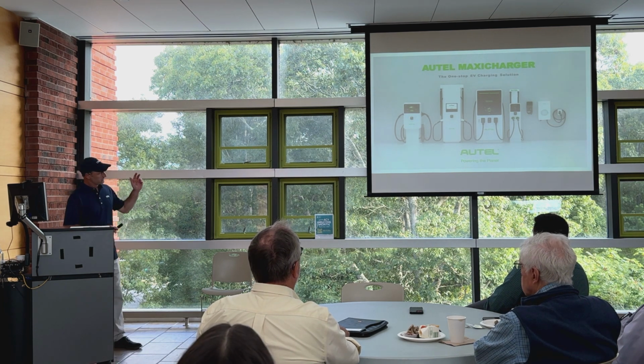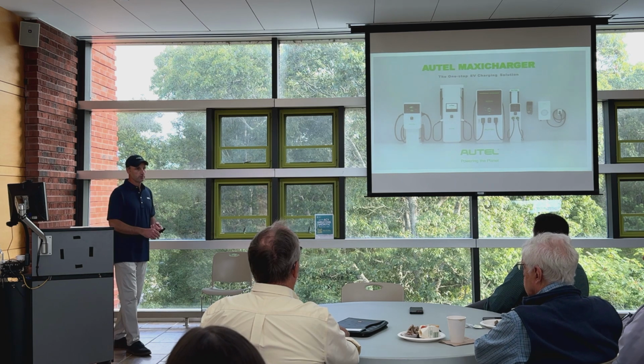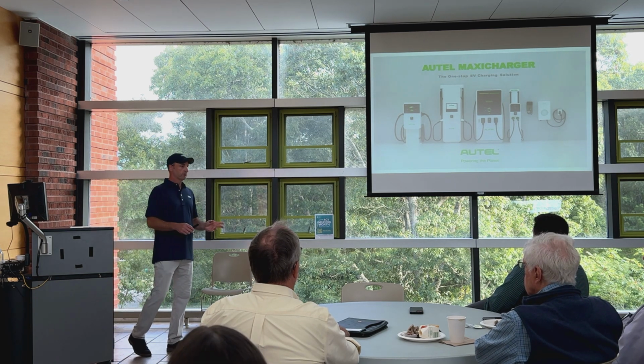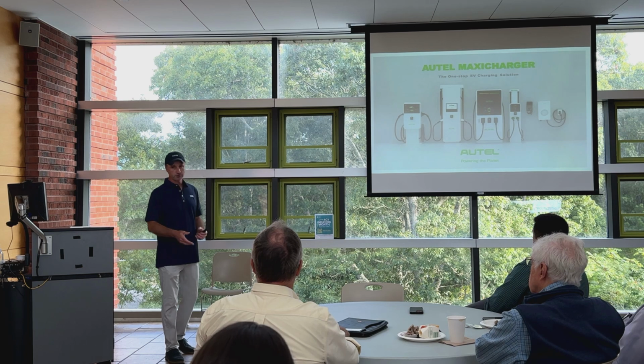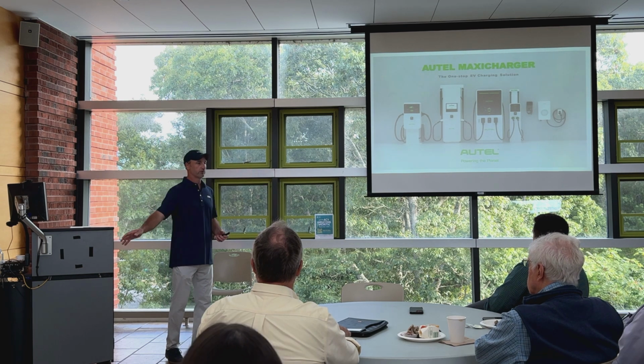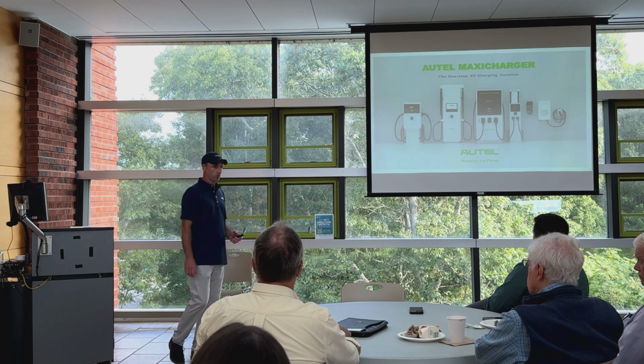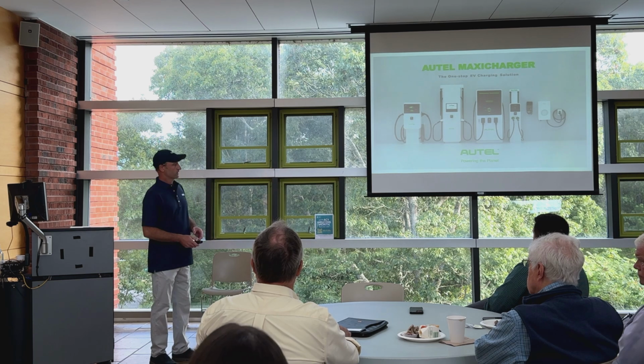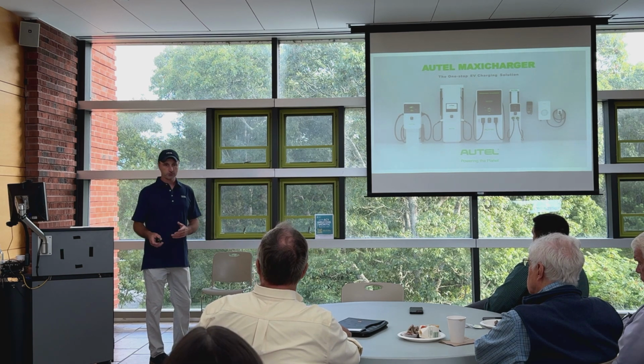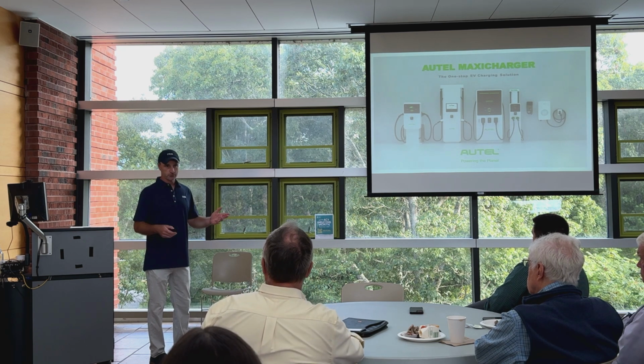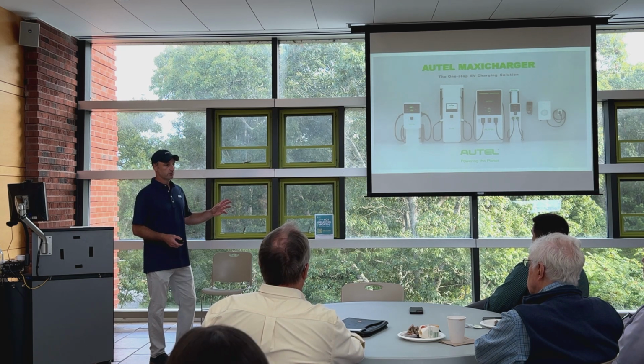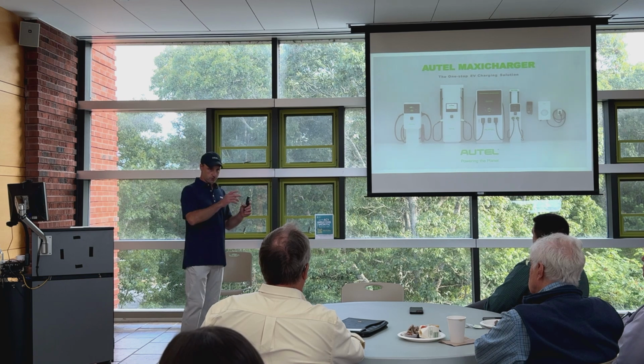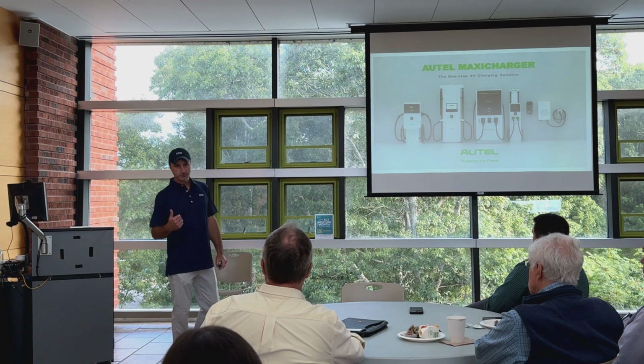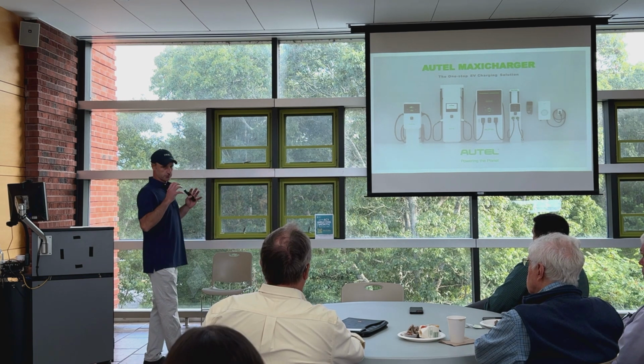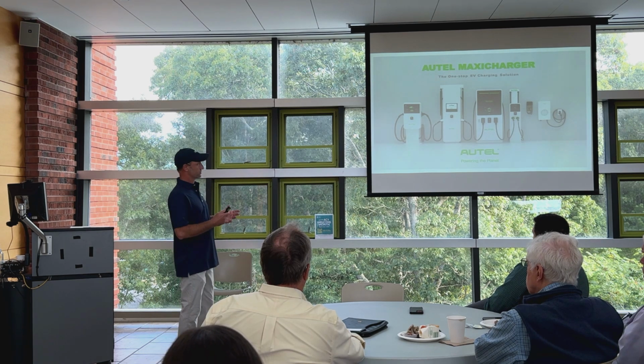So we talk about levels of chargers: level 1, level 2, and level 3. Level 1 is at your house, the 110 outlets all over in the living room, you can plug in just a regular cord. That's 110 volts, a level 1 home charging unit. Then level 2, which is home and commercial, uses 220 or 240, like your oven and your dryer. It's using 2 legs of 110 to bring twice as much energy in, so you get a bigger amount of energy able to be dispensed because your source is larger.